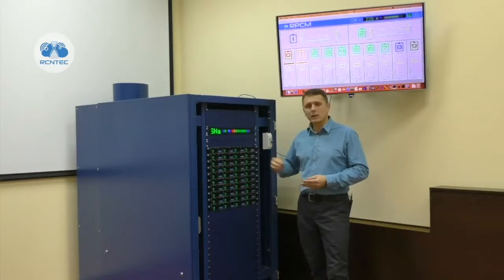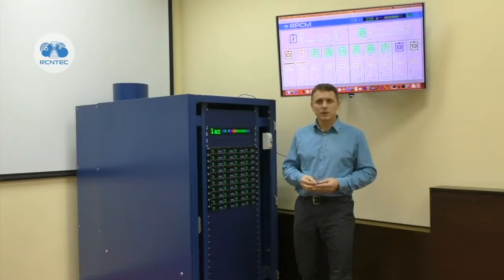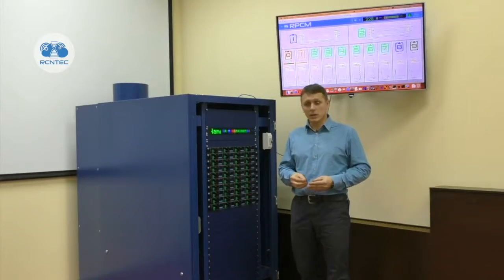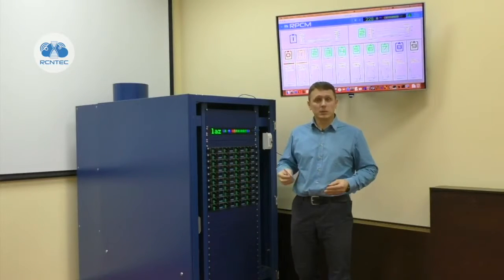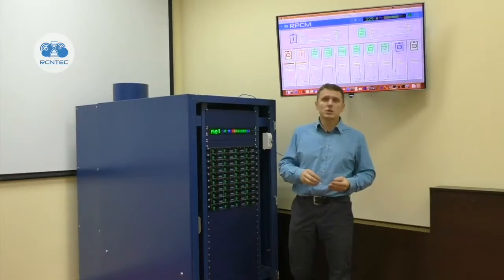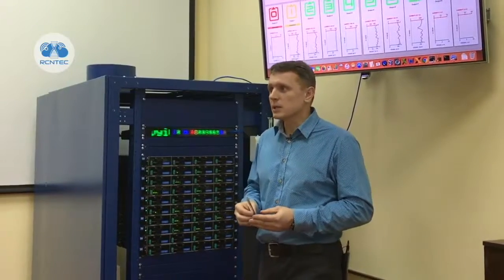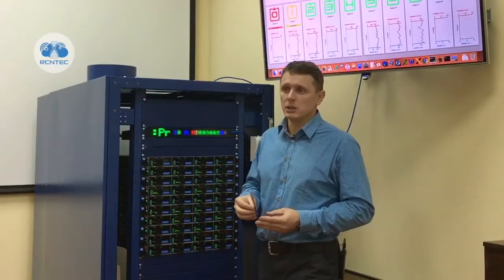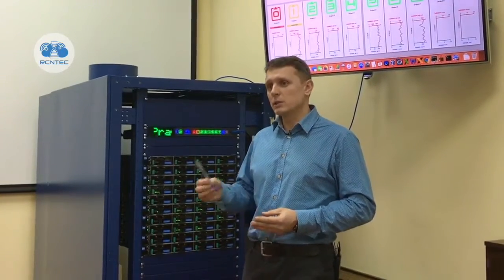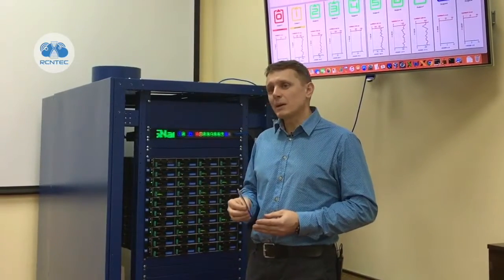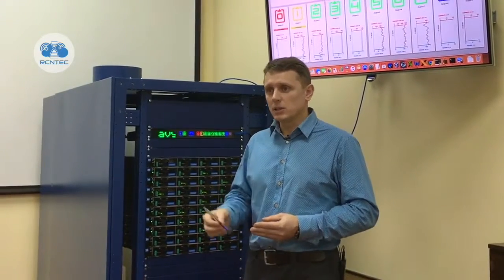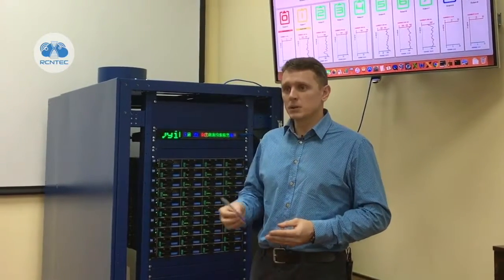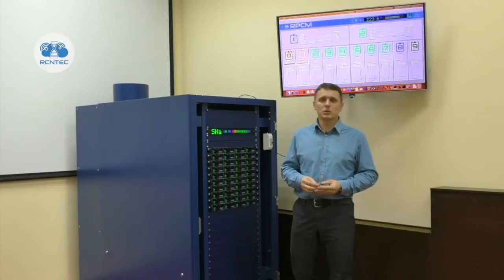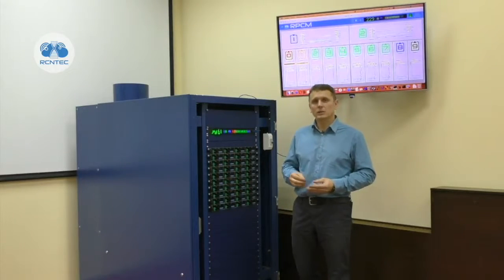In addition to switchover happening due to complete power loss, RPCM also switches over if power quality characteristics fall out of defined thresholds. Configurable voltage range for inlets is from 90 to 250 volts, frequency range is from 45 to 65 Hz. So if voltage or frequency on main inlet is out of range configured by the administrator, RPCM automatically switches consumers to second inlet without interruption of power supply to consumers.